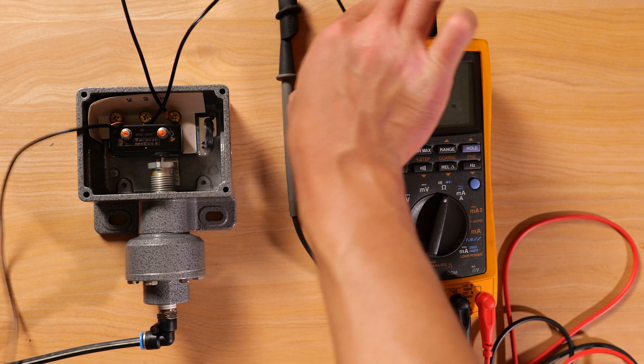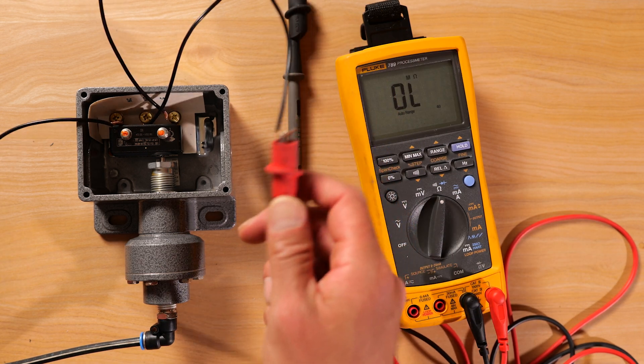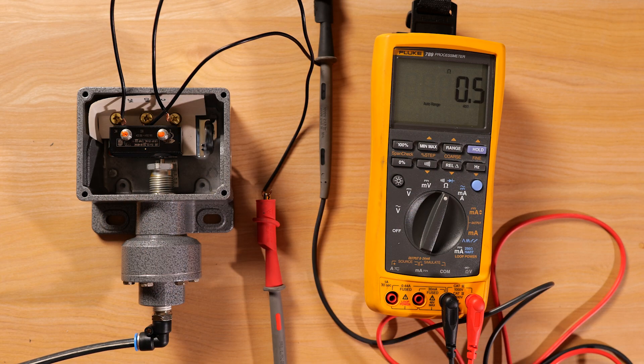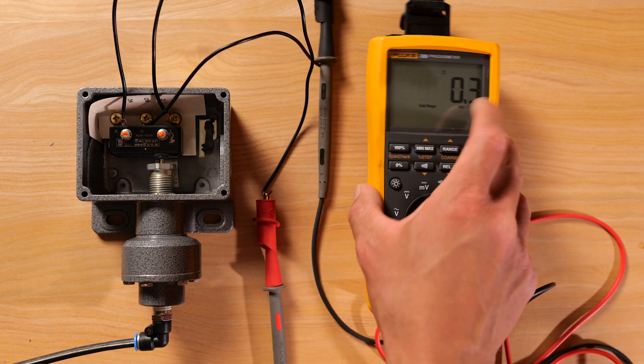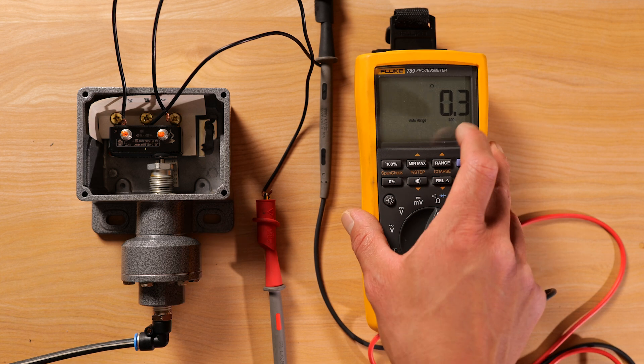So if we were to test that over to the common and closed without any pressure applied, right? So zero pressure applied as a process into the diaphragm, you have 0.3 ohms or you have continuity already.